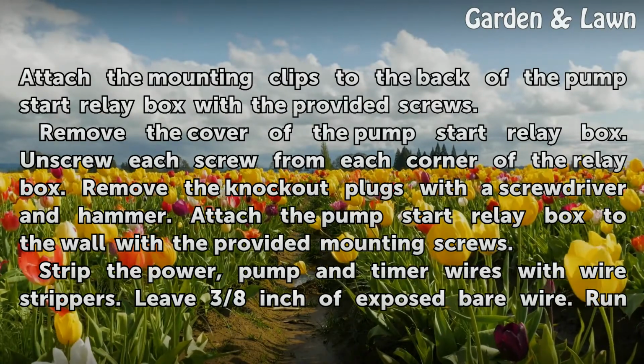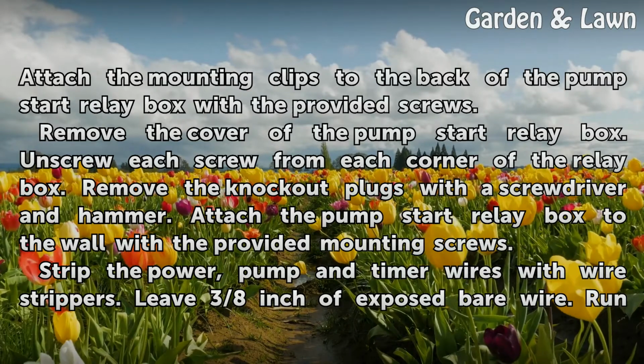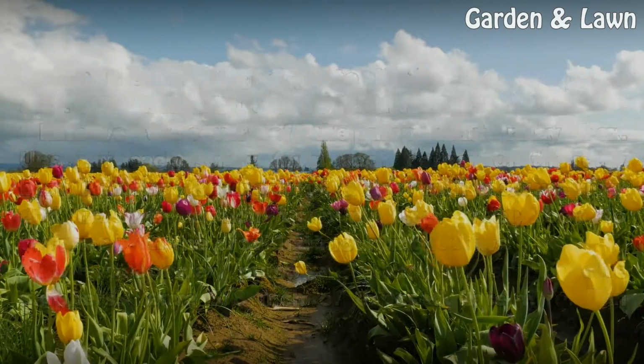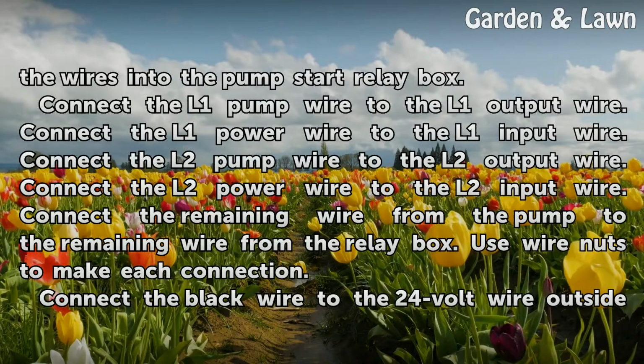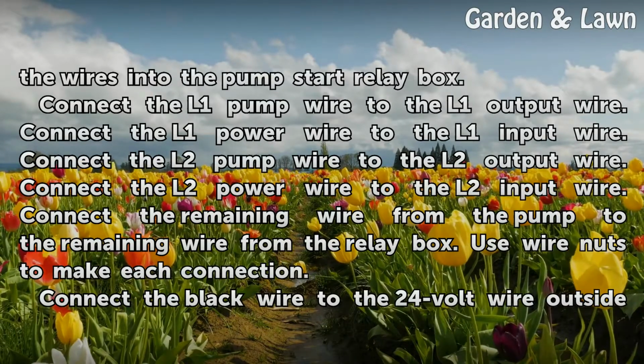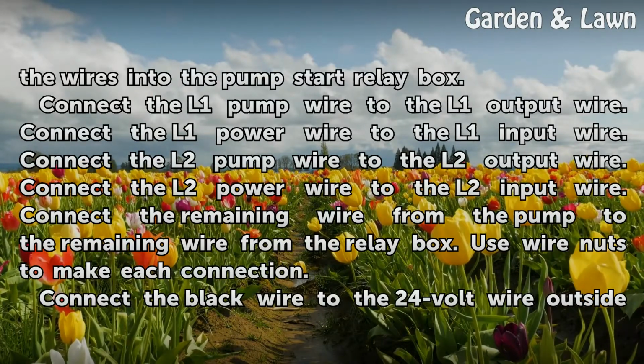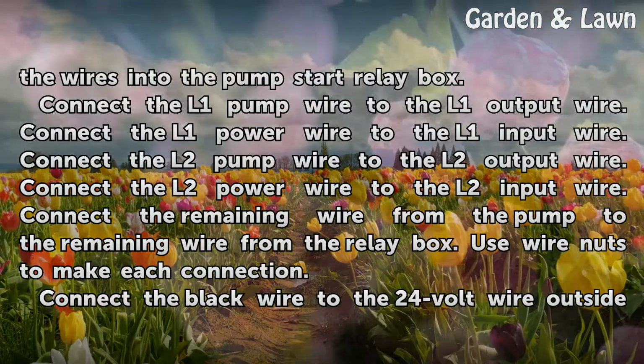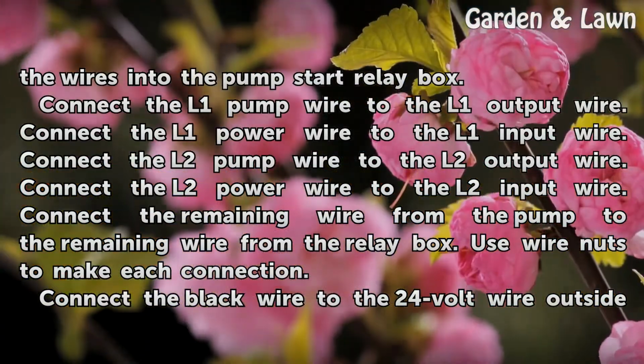Strip the power, pump and timer wires with wire strippers. Leave 3/8 inch of exposed bare wire. Run the wires into the pump start relay box. Connect the L1 pump wire to the L1 output wire. Connect the L1 power wire to the L1 input wire.